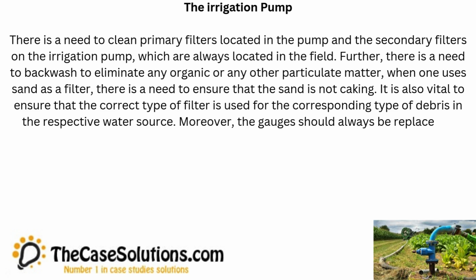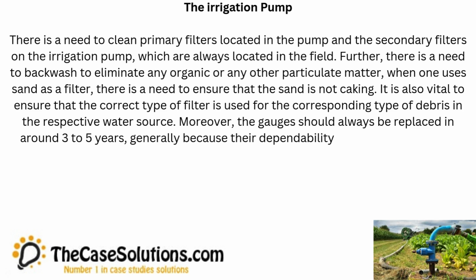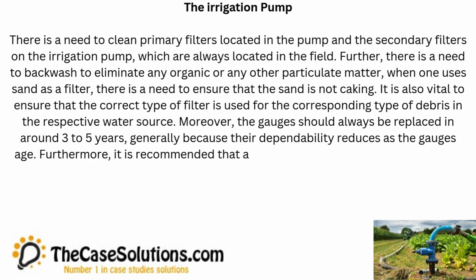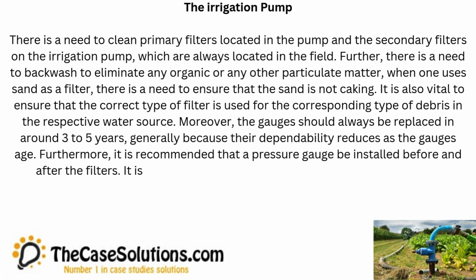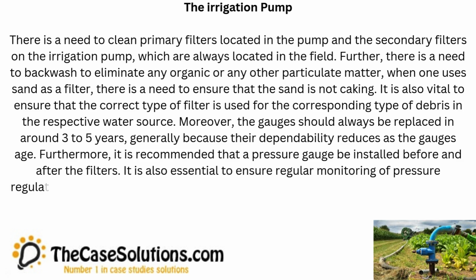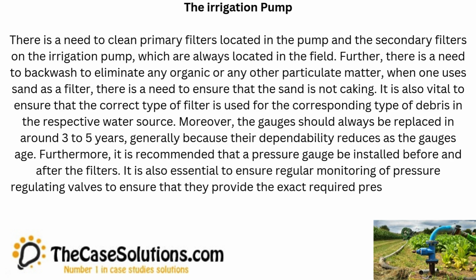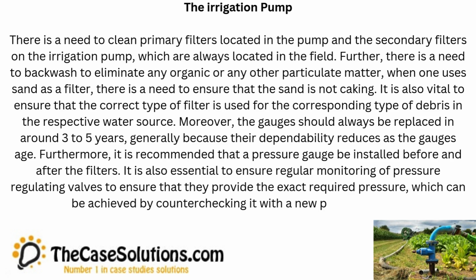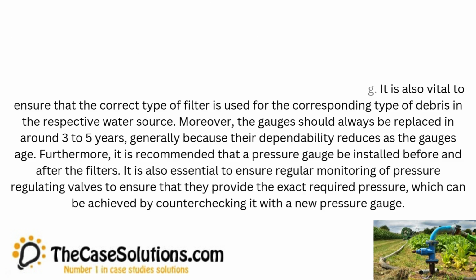Moreover, the gauges should always be replaced in around 3 to 5 years, generally because their dependability reduces as the gauges age. Furthermore, it is recommended that a pressure gauge be installed before and after the filters. It is also essential to ensure regular monitoring of pressure regulating valves to ensure that they provide the exact required pressure, which can be achieved by counter-checking it with a new pressure gauge.